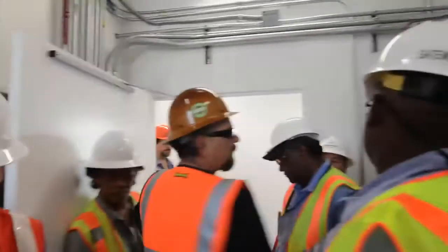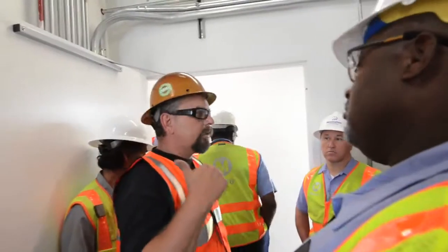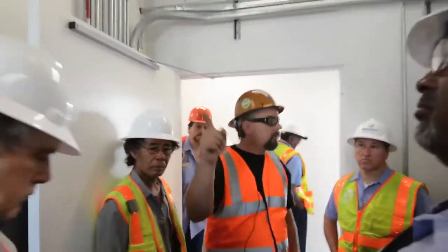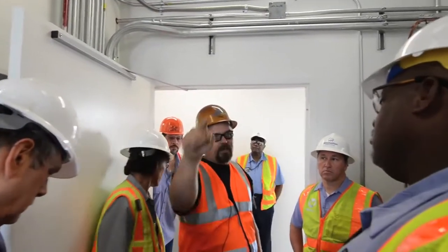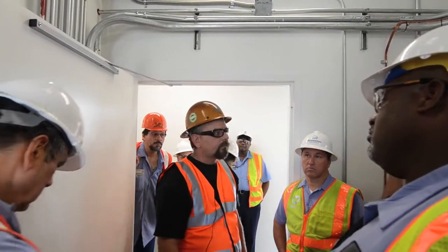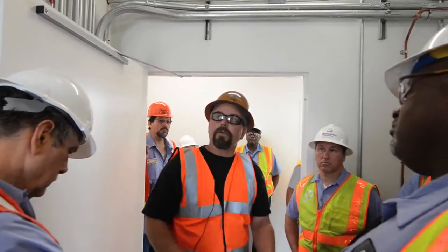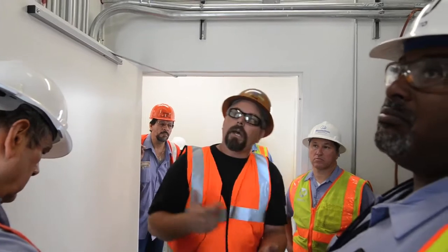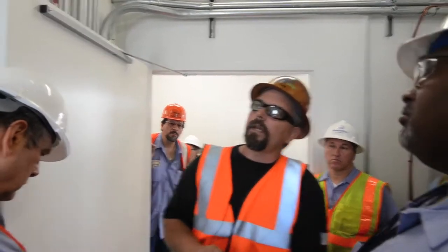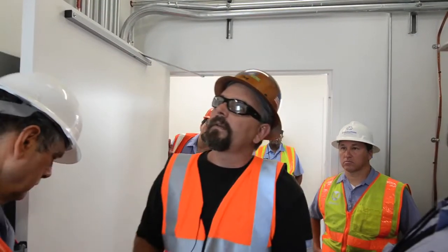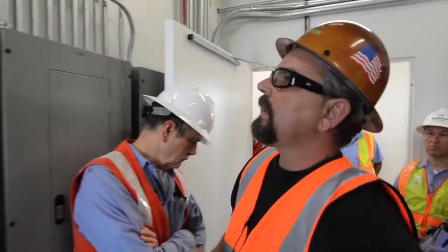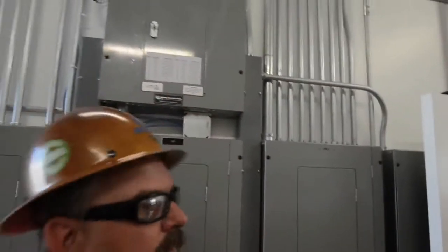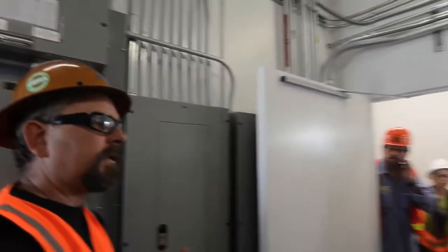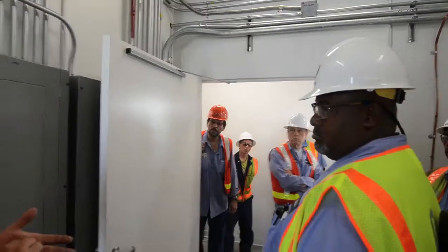Out here in the corridor, you have the controller. All the programming for even this panel and the next one I'm going to show you is done at the main, over there in the corner. So you would have to let it know — you would have to stand here and say, okay, at LCP1, I need relays 1, 3, 5, or whatever the numbers are, to be whatever your method of control is that you're going to change it to.